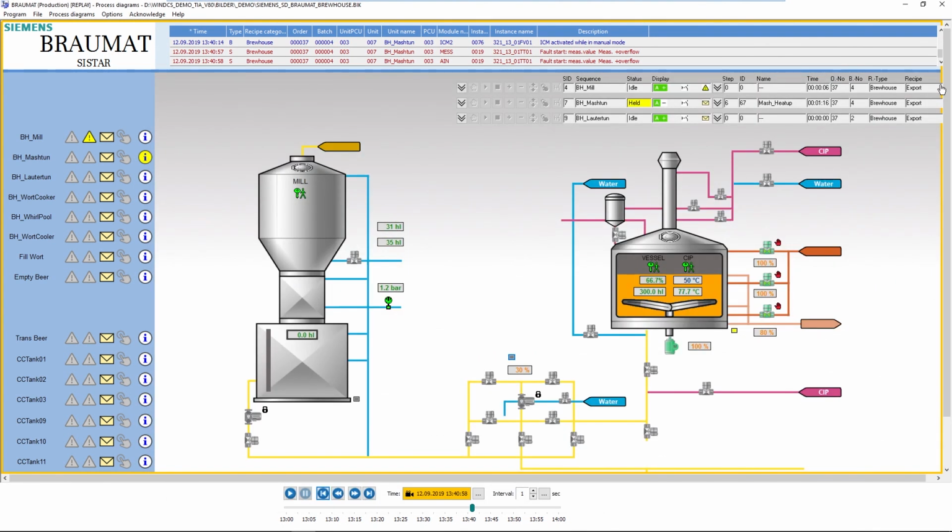Well, now we have a scenario and the operator might explain that at that time it was not possible to activate the steam valves via the automatic system. It was a mechanical defect. He had to put the process into a stable state, so it's on hold. And the operator manually monitored and started the heating process. In the end, his mistake here was not to pay attention to this limit.